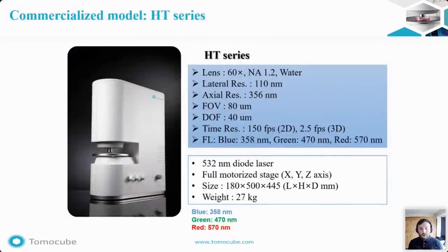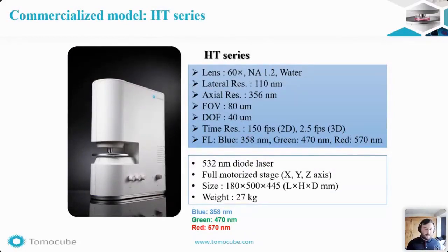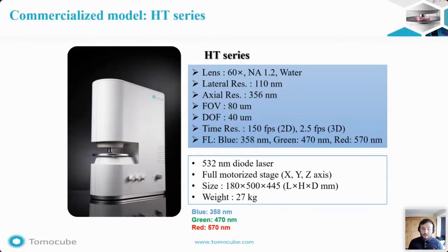The model I will talk about today is the HT2H, which includes fluorescence imaging. The refractive index measurements are acquired using a 60x water lens with an NA of 1.2. The maximum field of view is 80 microns with a depth of 40 microns, and this is the most popular setup of our system.